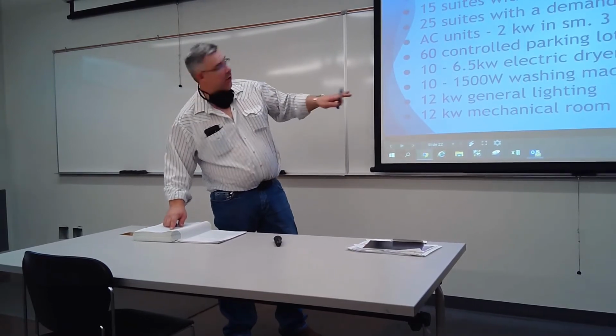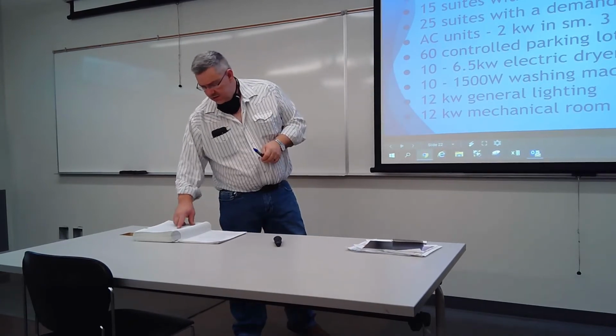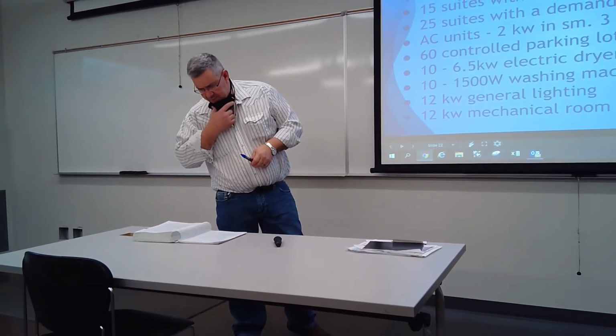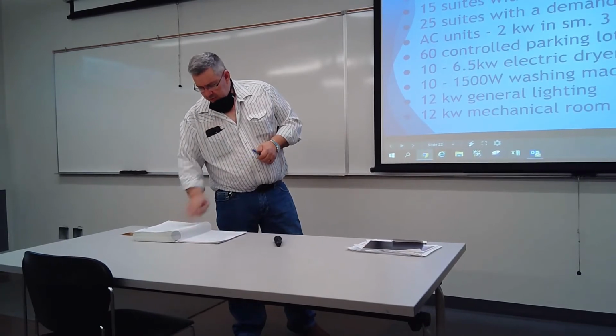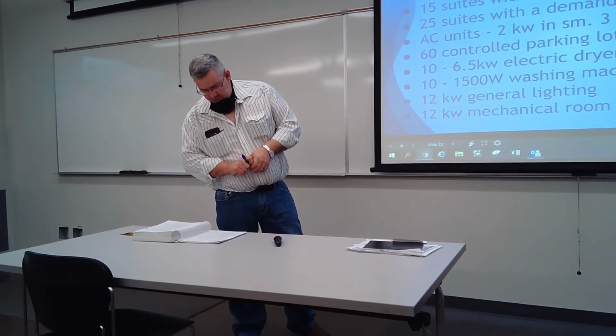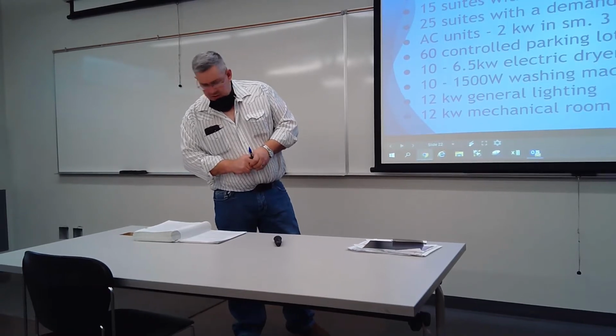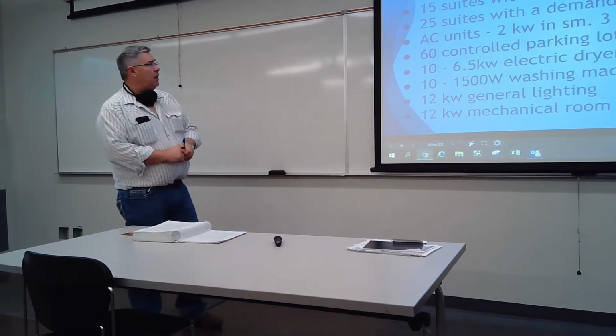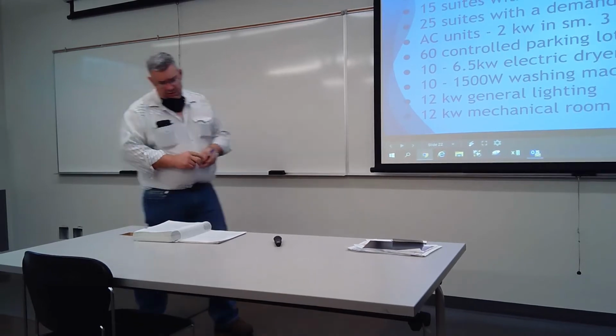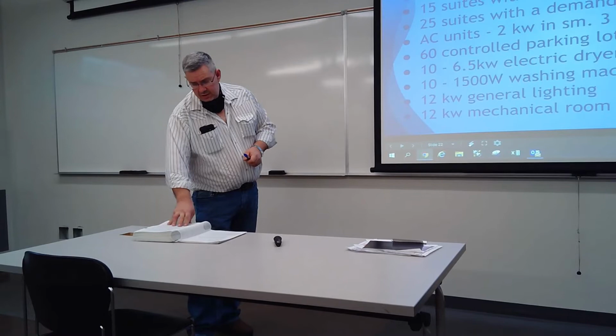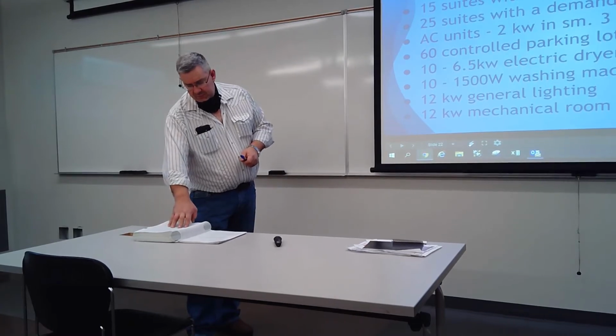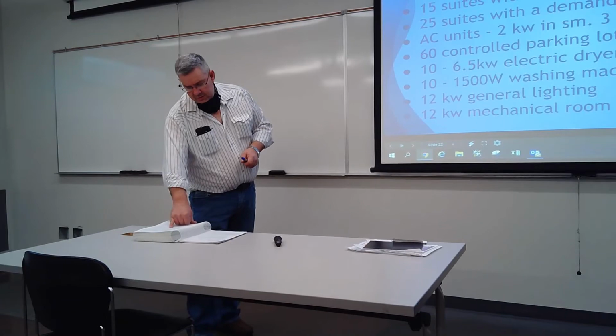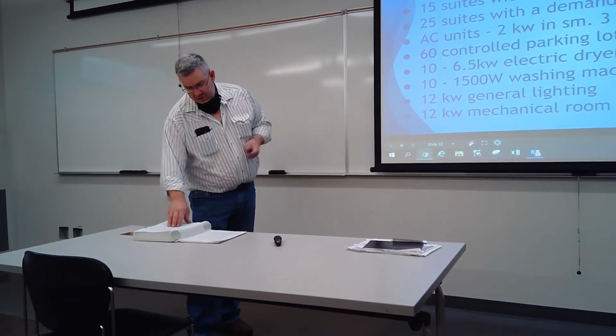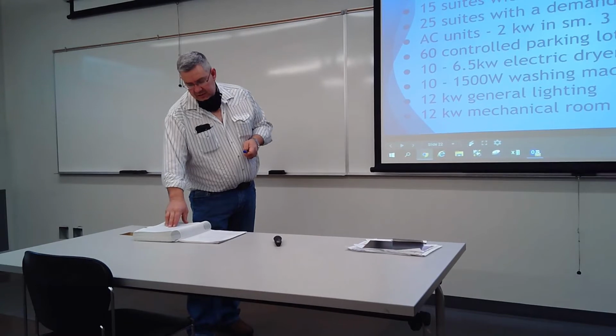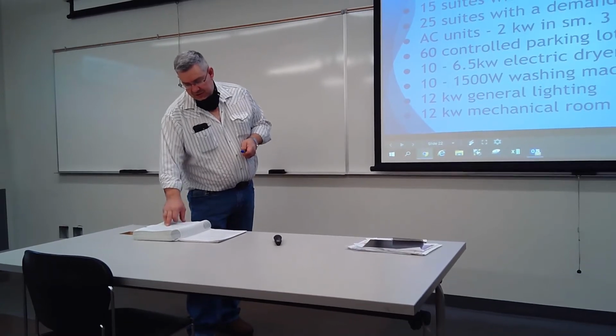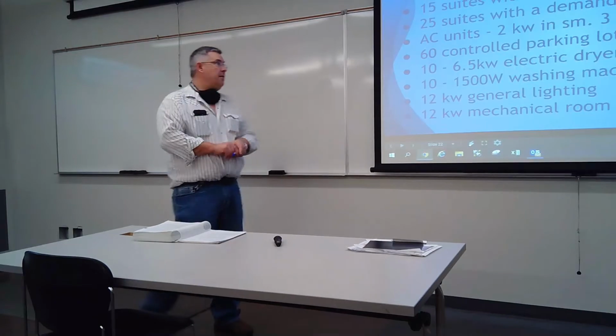One deals with how we came up with that 20 and 16 kilowatts. Number 2 just says that it's not a continuous load. So we're going to start in 8202 sub-rule 3. Excluding heat and air conditioning, the load shall be considered to be 100% of the load in the heaviest or the largest unit, 65% of the sum of the calculated loads in the next 2 units, 40% in the next 2, 25 in the next 15.